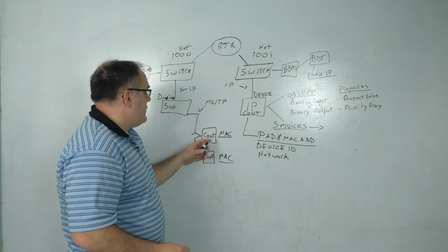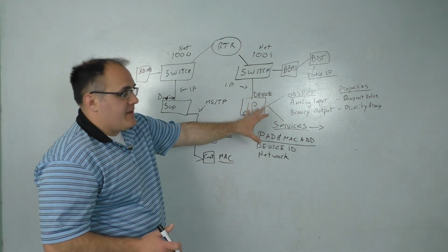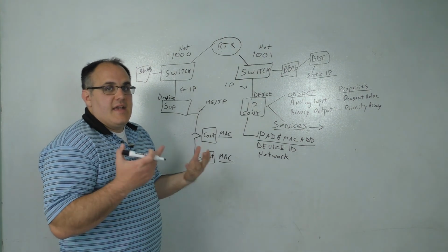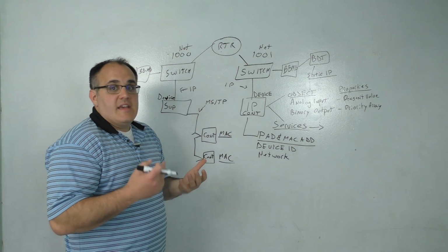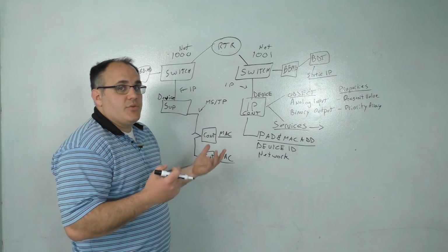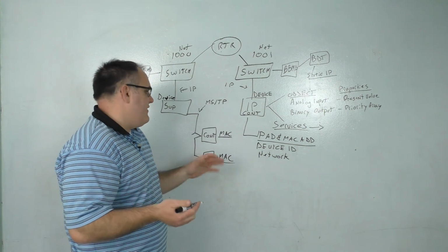But as I was saying, you have MAC addresses, where the MAC address on an IP device is a hexadecimal number, whereas the MAC address on a field controller is quite simply a series of dip switches that you flip to address it from 1 to 255.